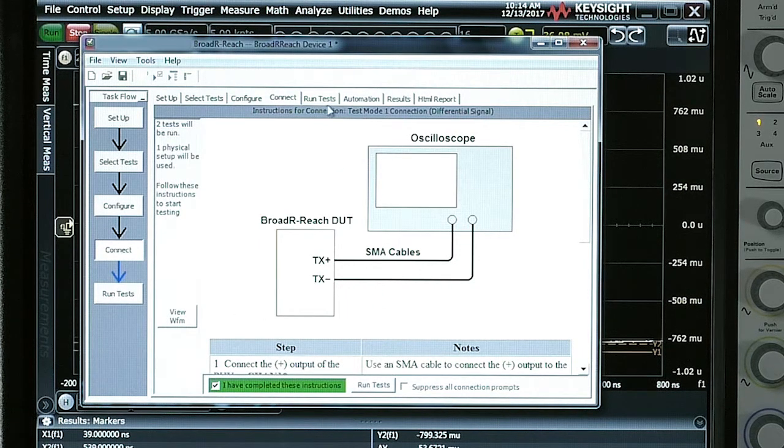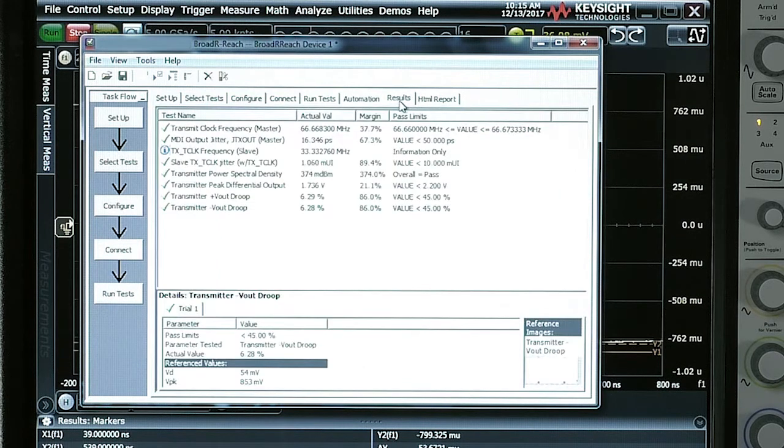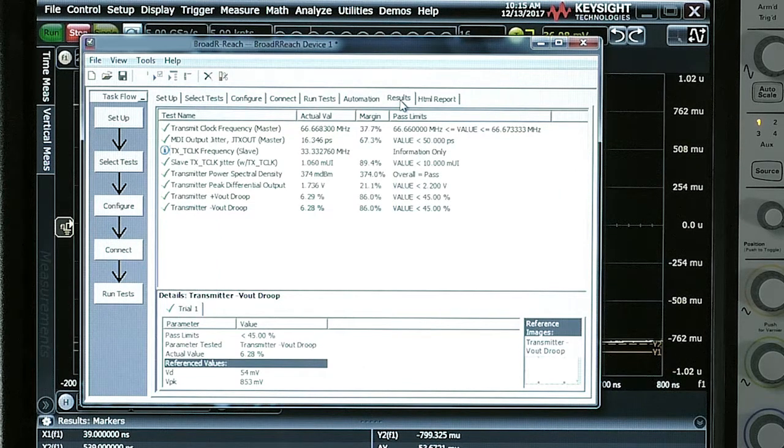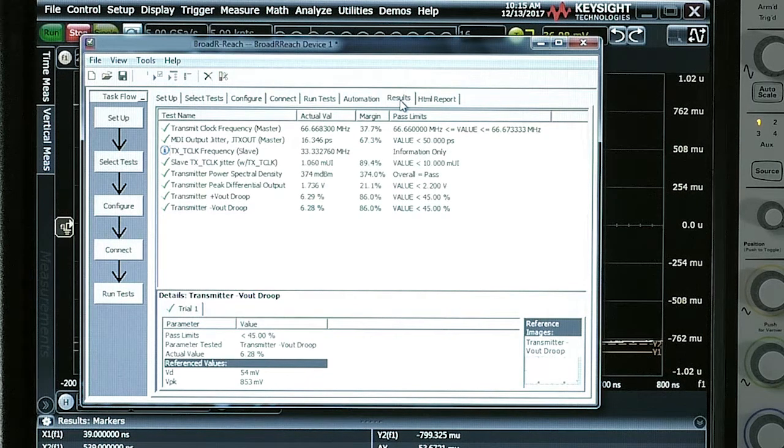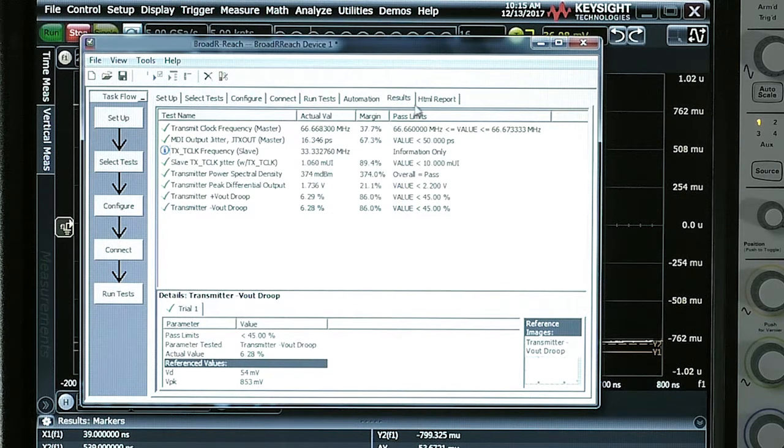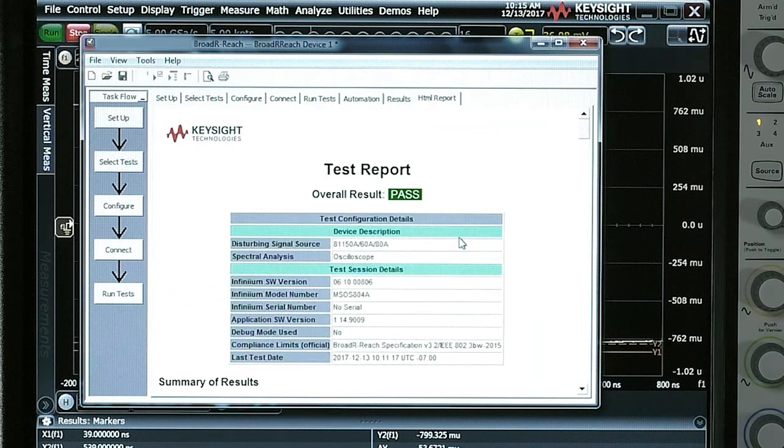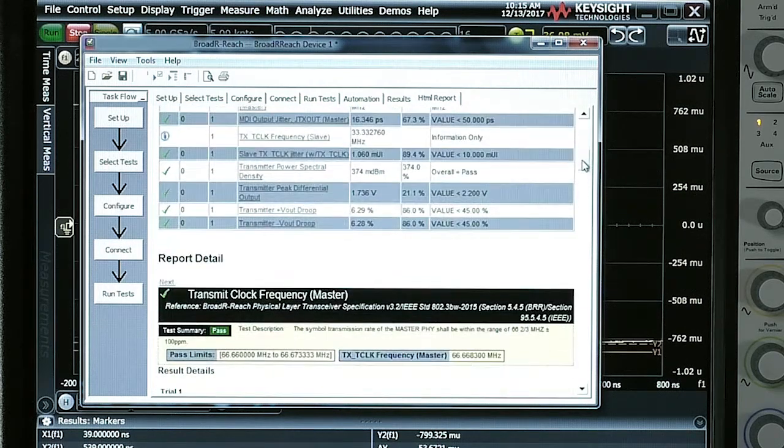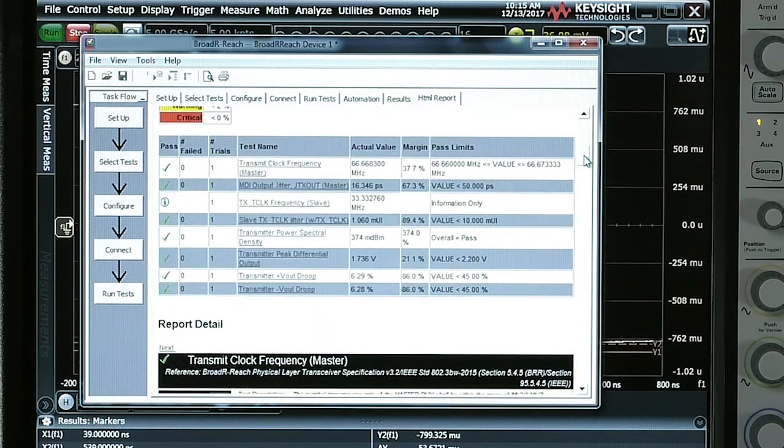Once you run the tests, you come back through to results and here you can see the pass-fail margins associated with each of those. Now I've run these tests already and you can see that they have passed and in addition to that there's an HTML report that allows you to look through the details of the screens and email this report directly to another user.